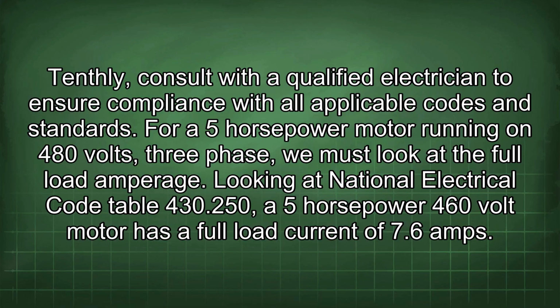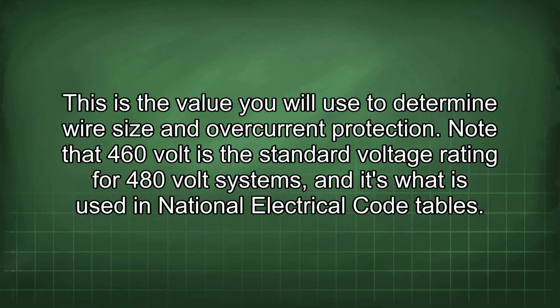For a 5 horsepower motor running on 480 volts, 3-phase, we must look at the full load amperage. Looking at National Electrical Code Table 430.250, a 5 horsepower 460 volt motor has a full load current of 7.6 amps. This is the value you will use to determine wire size and overcurrent protection.